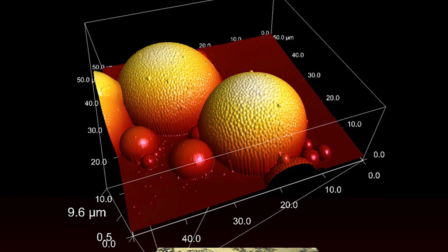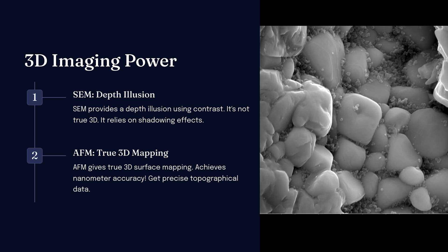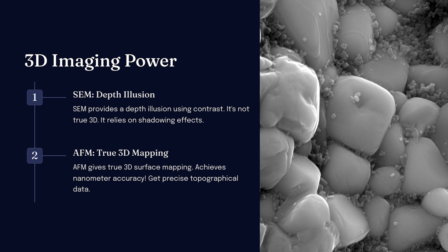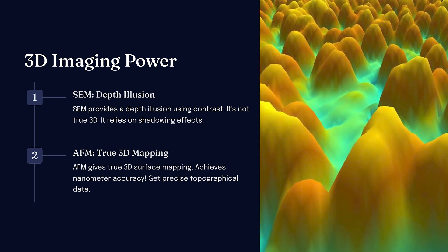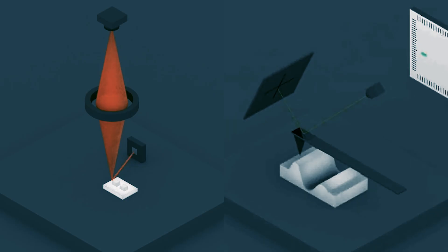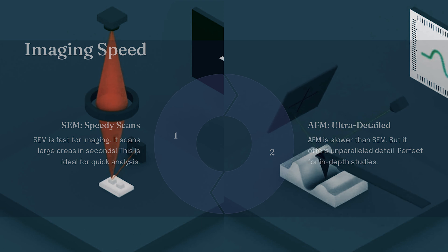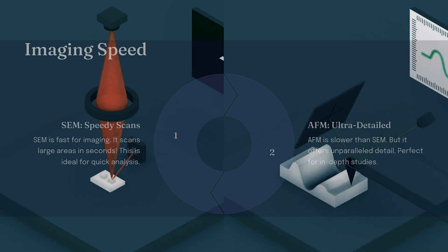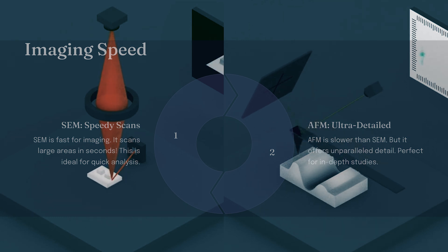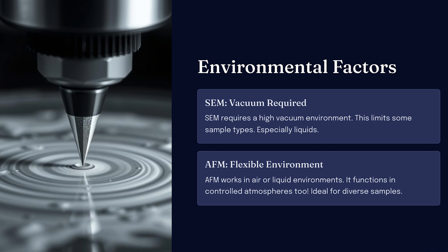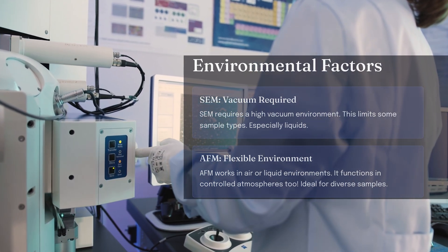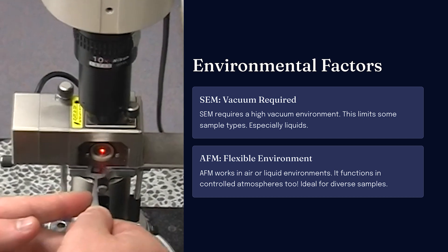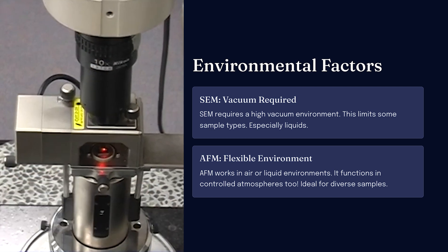What if you need true 3D imaging? SEM provides depth perception, but it's not a true 3D surface map — it relies on shadows and contrast to infer depth. AFM, however, directly maps the surface in three dimensions, creating high-accuracy 3D reconstructions at the nanometer scale. Need results fast? SEM is much faster than AFM and can scan large areas in seconds, making it perfect for high-throughput analysis. AFM, though incredibly detailed, is much slower since the probe must physically scan the surface point by point. SEM also requires a vacuum environment, which can be a major limitation for biological samples. But AFM can operate in air, liquid, or even specialized environments, making it a more flexible choice for sensitive samples.